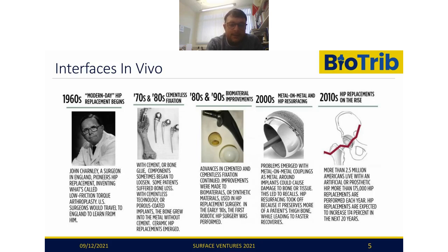But essentially, these devices were demonstrated to be lower wearing and better performing than the traditional metal on polymer systems. And so they were implanted in their droves in both younger patients and older patients. And ultimately, within 5 or 10 years, we saw that there were massive complications in terms of metal ion release and metal particulate release, as these things started to degrade in a way that we didn't really know or understand.